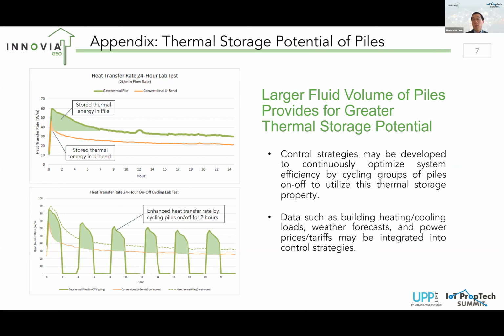Sure, so your first question there. The typical wells that are 300 to 600 feet deep, they don't have to be that deep, but typically conventional systems are drilling under the building footprint, so there's a space limitation. They're usually going that deep because they've got to get the length to be able to get the capacity they need. There are horizontal systems out there that are only about 7 to 10 feet deep that lay the pipe horizontally, but they just need the space there.